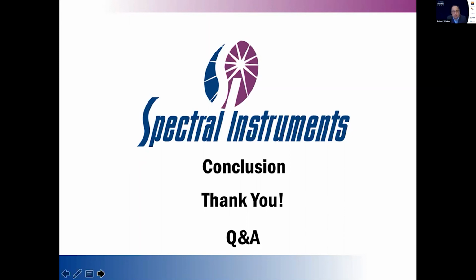Another question: what is the spectral wavelength range you have for testing capability in your Tucson facility? Well, most of our testing is done with optical. We do also have some X-ray sources, but most of ours is in the optical wavelengths. Currently, we don't have anything set up for ultraviolet. So visible wavelengths, and then some X-ray here. We have more X-ray facilities up in Evanston, because those detectors are all calibrated using soft X-rays from the 5 to 20 keV range. They've got a good facility for that. And then, of course, at Direct Electron, they have the facilities for the electron detection, both soft and hard X-rays, or electrons.